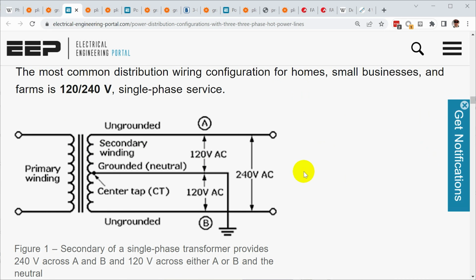The most common wiring distribution configuration that's in homes and businesses, farms, whatever, in North America is 120 volt or 240 volt split phase. Now, what that means is you have a transformer that is supplying power to the building, and you have a single 240 volt AC phase that's being provided as input. That is run through a transformer that is center tapped. So you have a center tap on the transformer that is then bonded to the earth ground, and that's called the neutral. So what's actually coming into your panel is a neutral that's referenced to earth ground, and then two legs of power that are each 120 volts AC with reference to that neutral.